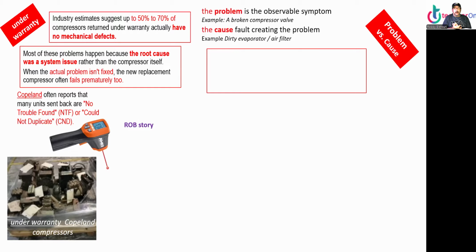Now, the problem and the cause. The problem is the symptoms. Example, a broken compressor valve. The cause is the fault that created the problem. Example, a dirty evaporator, bad airflow, or a bad expansion valve will cause a broken valve.